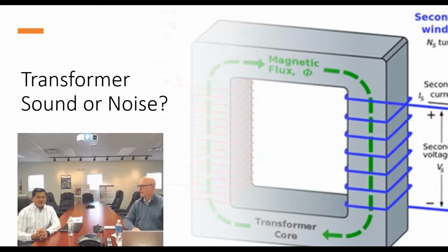Right? Thank you. So the question here is, is the transformer a sound or a noise? Anything that we hear is a sound. I'm speaking right now in front of you, that's a sound. That's a sound pressure created by the waves, which is being absorbed by your ears. But when this sound becomes annoying or unwanted, then it becomes noise. Now, as the transformer industry is modernizing, substations are being modernized, and we have more substations nearby residential or commercial areas. So that's why it becomes necessary to reduce the transformer noise and unwanted sound, so that it gives comfort to the nearby occupants. And then I would think it also improves the life of the transformer if you reduce the noise. Certainly it will, and I'll explain it in the next slides. Okay.